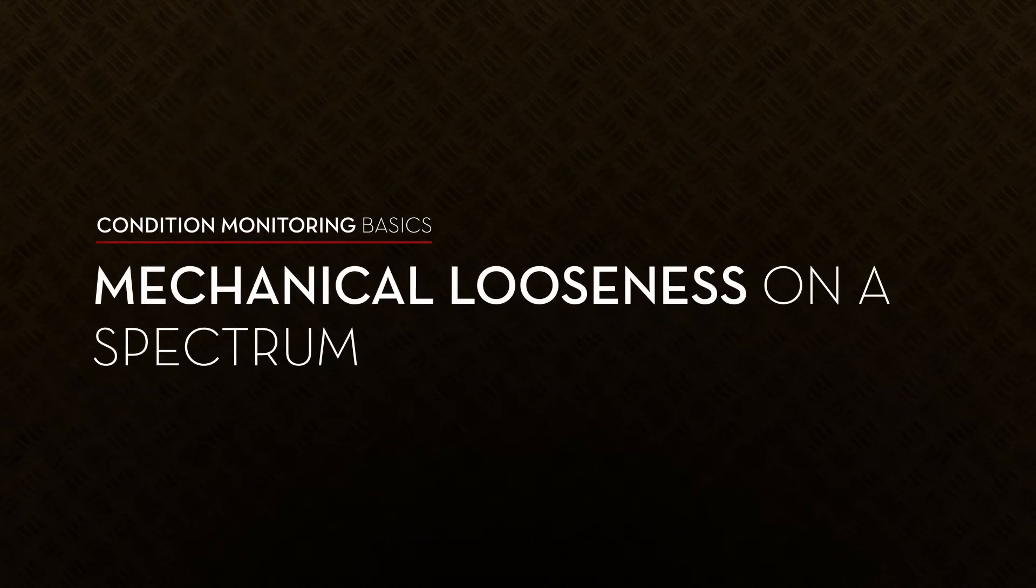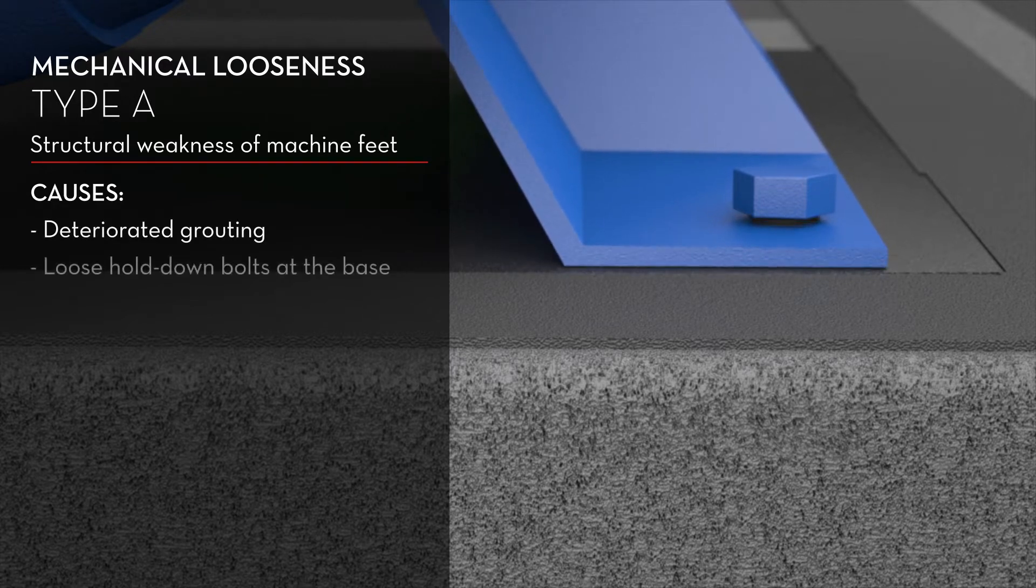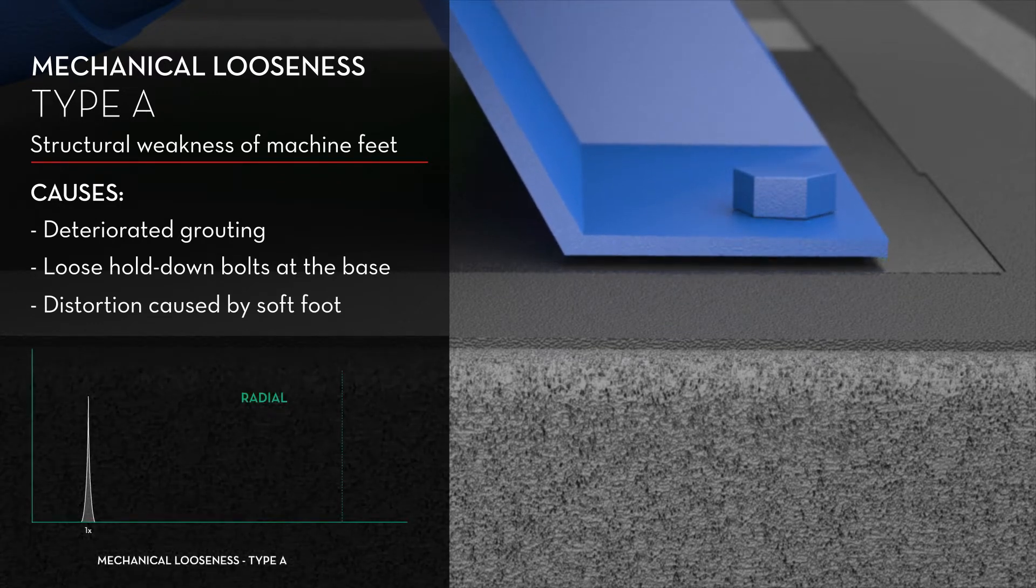There are three types of mechanical looseness. The first type, type A, is structural weakness of machine feet. It can be caused by deteriorated grouting, loose hold down bolts at the base, or distortion caused by soft foot. Type A appears on the spectrum as one pulse per revolution.